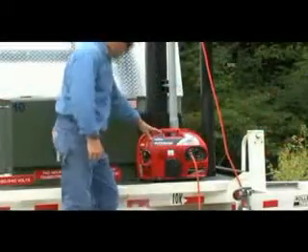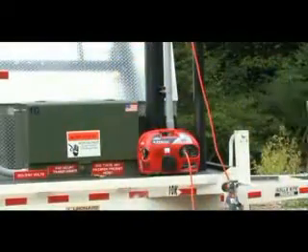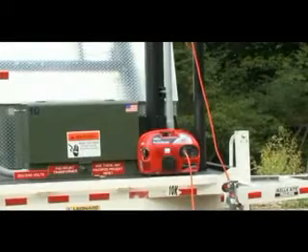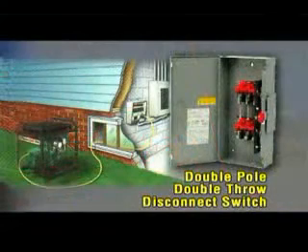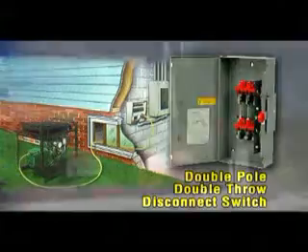Portable generators, such as this one, can pose a serious threat to our line workers when installed improperly. In this demonstration, a portable generator is improperly connected to the trailer. By this, we mean it is not connected to a double-pole, double-throw disconnect switch as required by the National Electric Code.